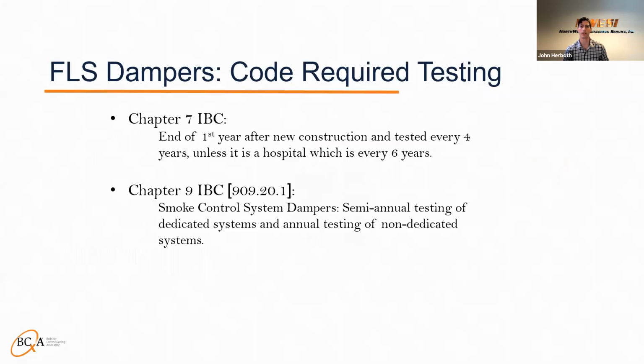This is another code pull from Chapter 7 of the International Building Code and Chapter 9. You're going to see this in multiple states for fire code as a reference point, as well as NFPA 80 and 105. So take a look at what your fire code is for your state or city, and you'll often see references to NFPA 80 and 105, which reinforce the 4 and 6 year damper testing.